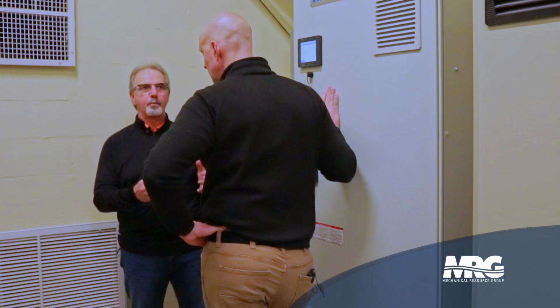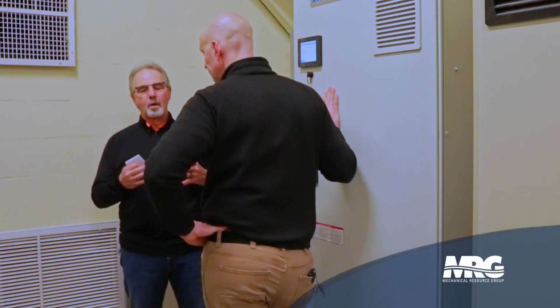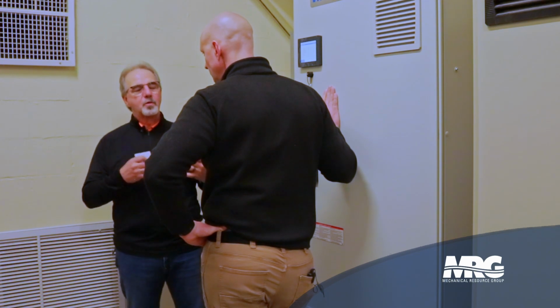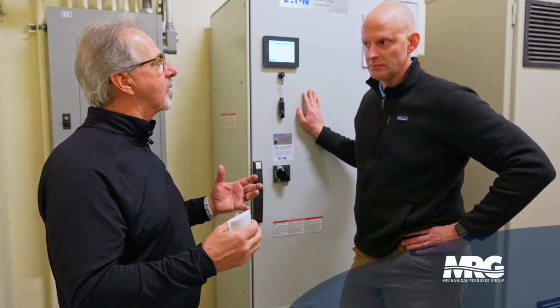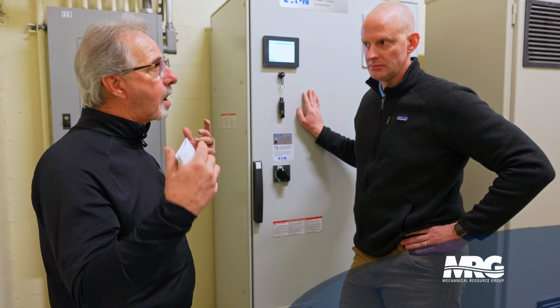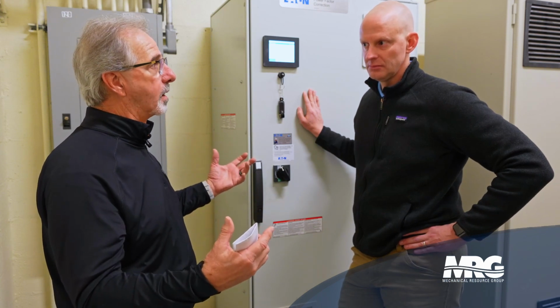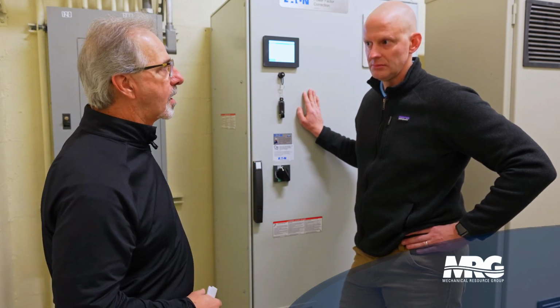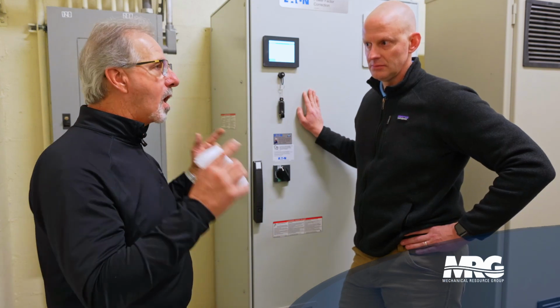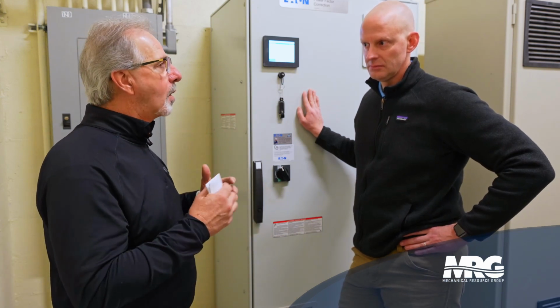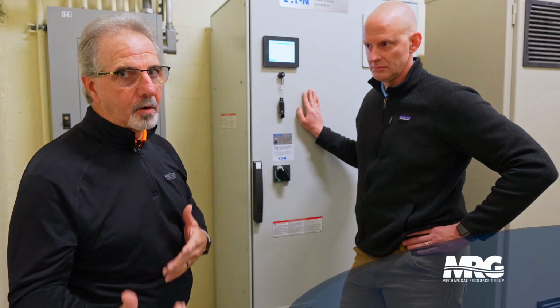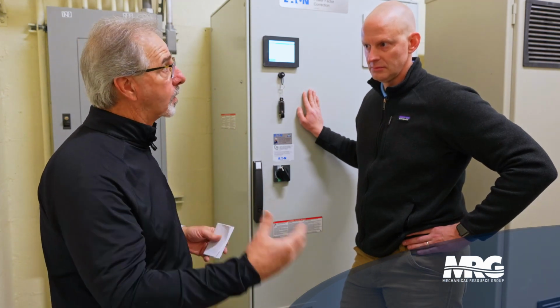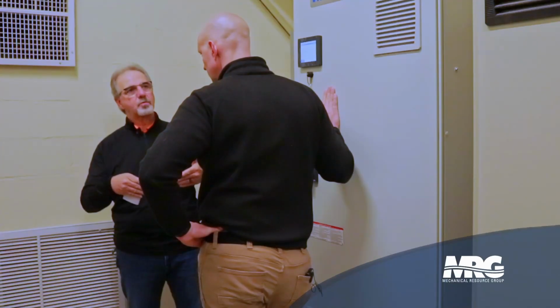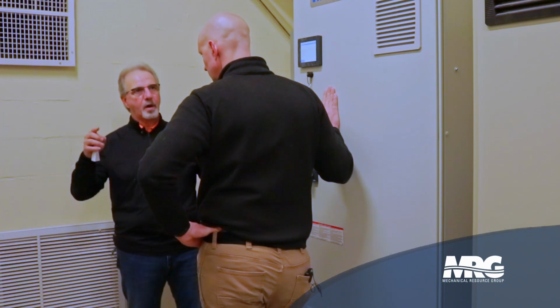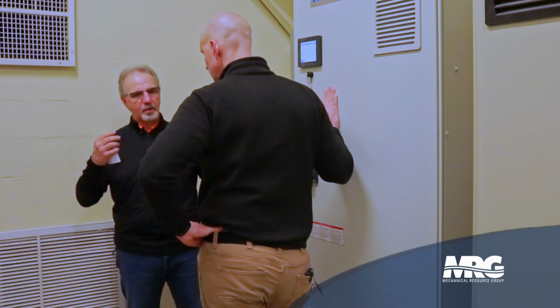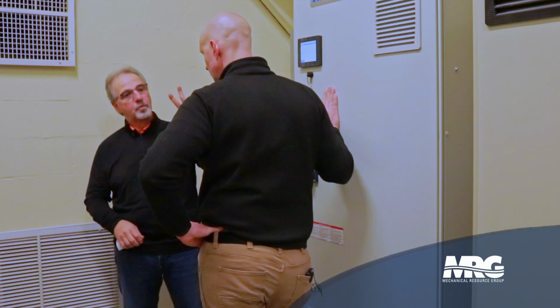People can live without power. People can't live without water. Yeah. So we want to make sure that they're able to do that. So we had to take the point of view of, okay, when this comes back on, all 3 drives are going to come up and run. So we had to time the generator to handle all 3 of these loads. Now, we don't have inrush, so it's not a current problem. What it is, is a voltage source problem. Syncing that generator in, recognizing all 3 harmonic loads, and syncing in and turning power on so that the transfer switch can make.